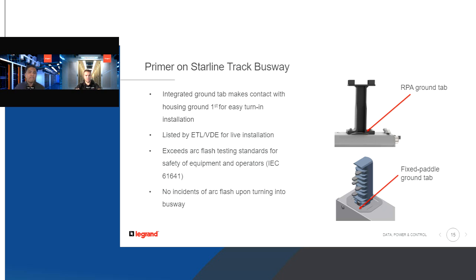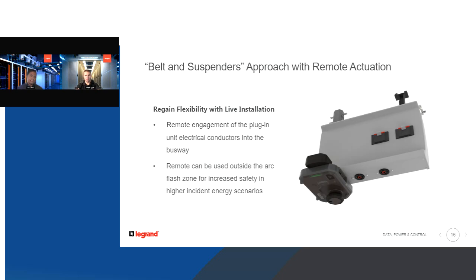So we've innovated the product in a way where you can step out of that arc flash boundary and still remotely engage the plugin. We've modified the tap box so that it rotates, and I'll show you an image of that shortly. This little device on the bottom of the tap box allows personnel to be outside the arc flash zone and remotely engage the electrical conductors into the busway.